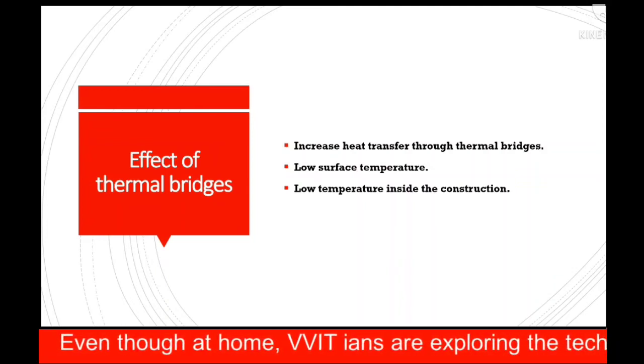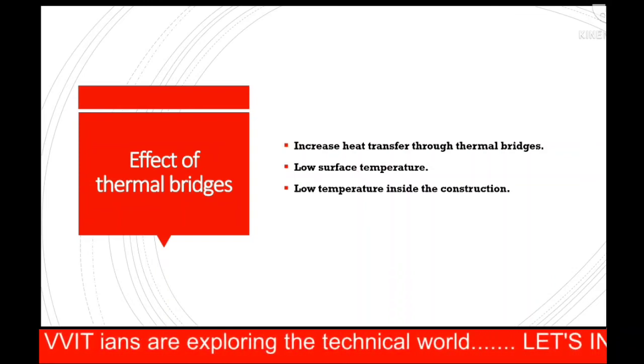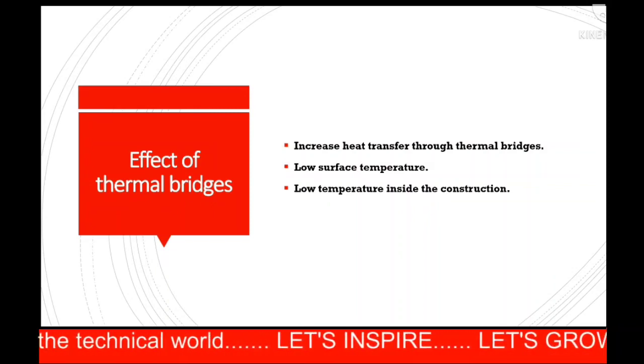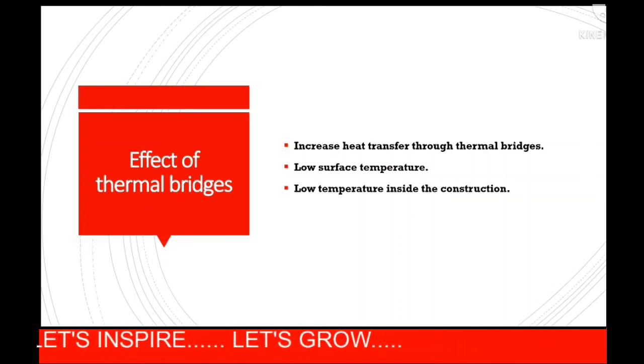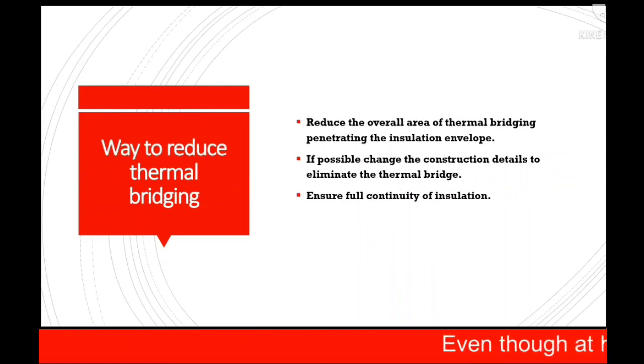Additionally, when the temperature difference between indoor and outdoor space is large and there is warm and humid air indoors, such as a condition experienced in the winter, there is a risk of condensation in the building envelope due to cooler temperature on the interior surface at thermal bridge locations. Ways to reduce thermal bridging.